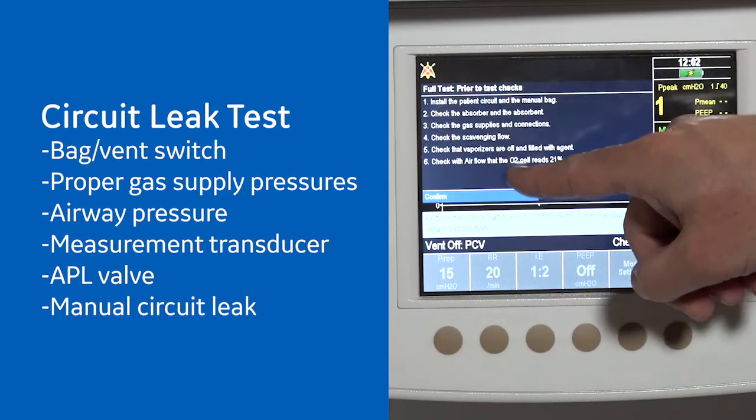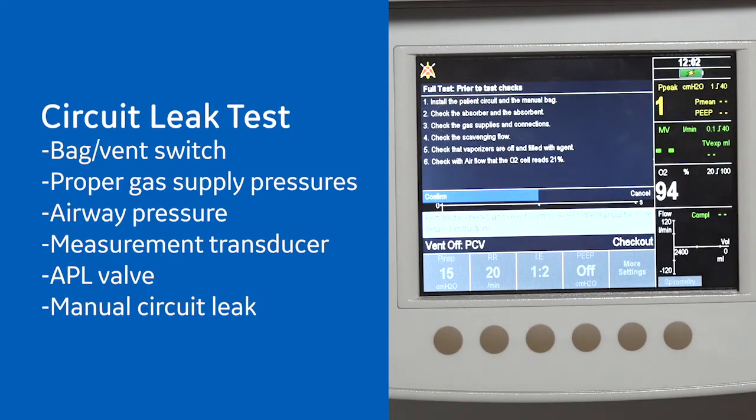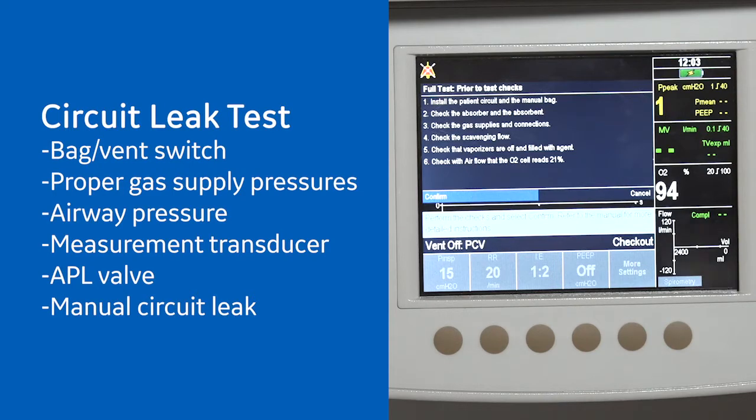The circuit leak test checks the bag to vent switch, proper gas supply pressures, airway pressure measurement transducer, APL valve, and manual circuit leak.